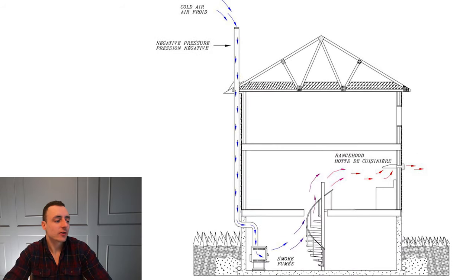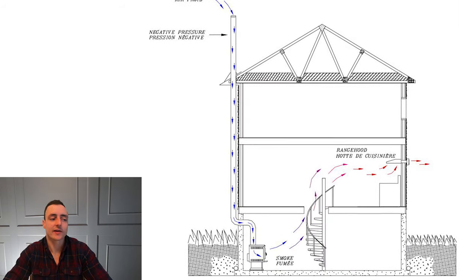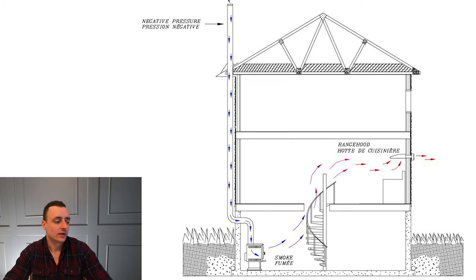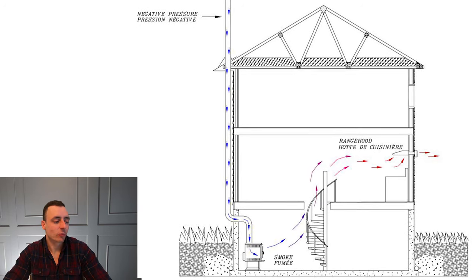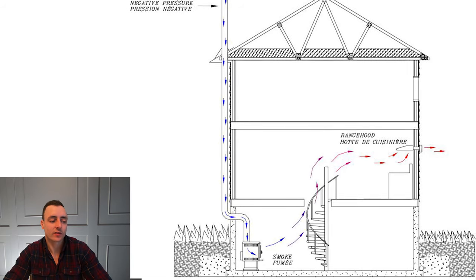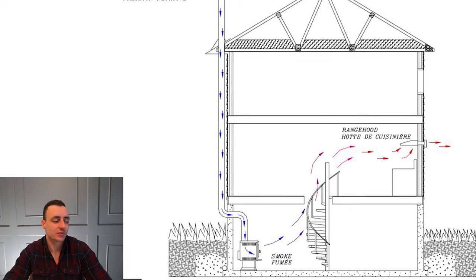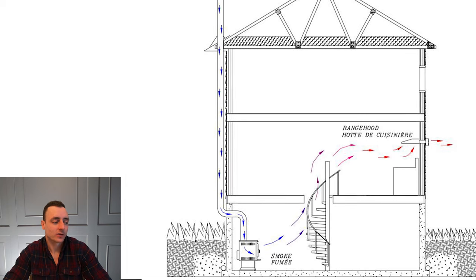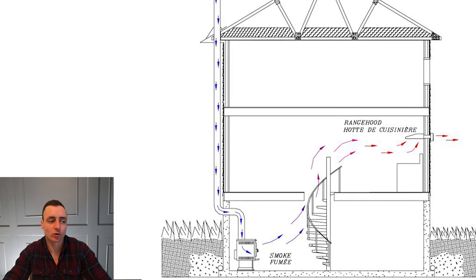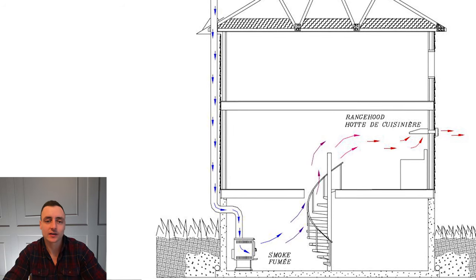Our third scenario shows the effect of negative pressure caused by an air-moving device inside the house. In this example, we see a range hood drawing air from the inside of the house, which is then replaced by air coming down from the chimney. The result is a smoking problem — that range hood is effectively sucking air out and reversing the chimney flow.